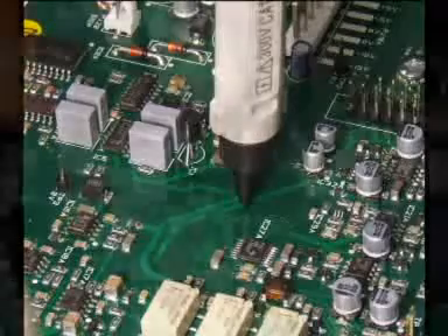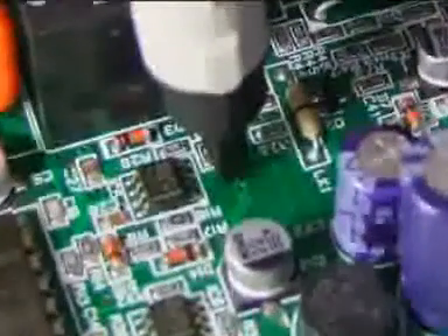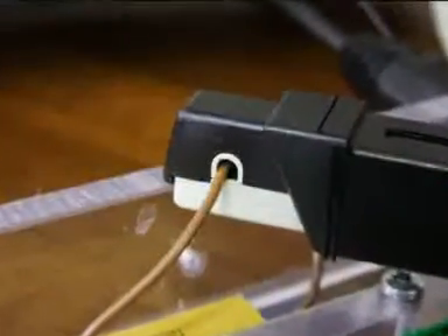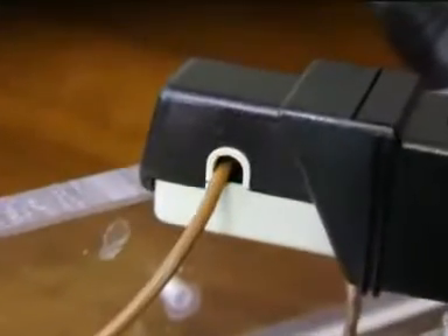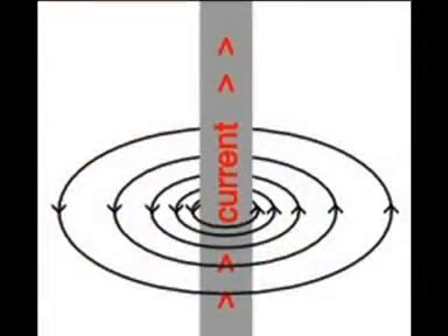We haven't managed to change the laws of physics here. What we are actually measuring is the magnetic field that results from the current flowing through the conductor. That's exactly the same thing as is measured by a conventional loop current probe. However, these probes work by capturing the whole of the field by surrounding the conductor with a loop of high mu material such as ferrite.